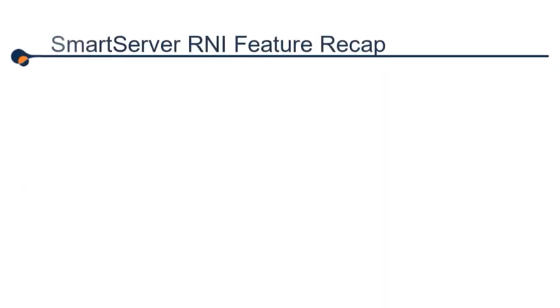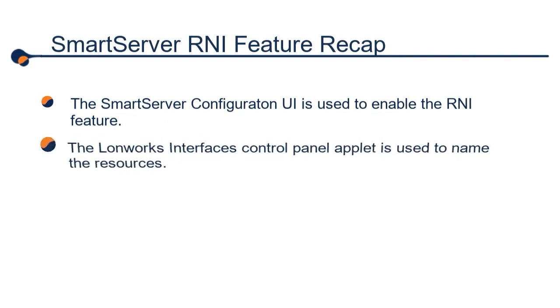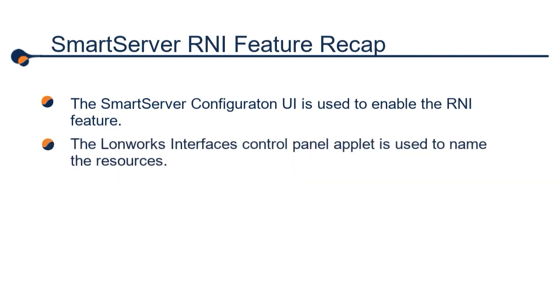So let's have a quick recap. The RNI feature is not enabled by default on the smart server. You need to use the configuration UI and the LON tab to enable one or more RNI resources if you wish to use OpenLDV. The LonWorks Interfaces 32 control panel applet is used to name the devices and define the IP addresses and ports that are used for these RNI resources. Applications use the named X.Default assets to open these interfaces.